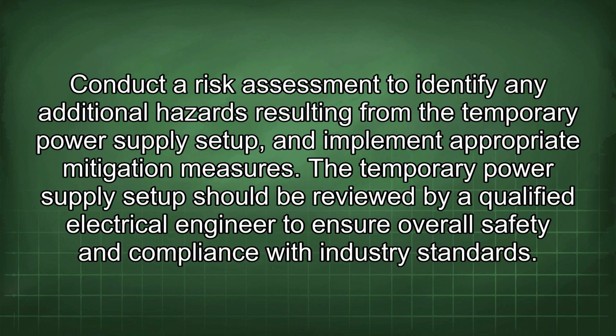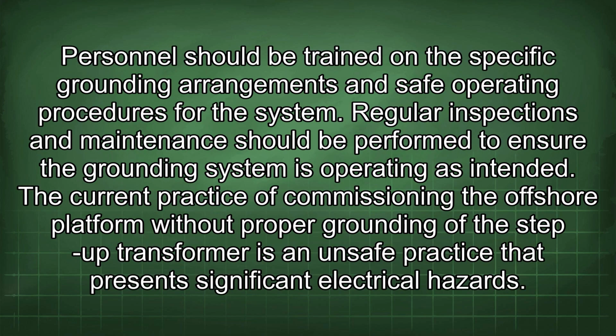Conduct a risk assessment to identify any additional hazards resulting from the temporary power supply setup, and implement appropriate mitigation measures. The temporary power supply setup should be reviewed by a qualified electrical engineer to ensure overall safety and compliance with industry standards. Personnel should be trained on the specific grounding arrangements and safe operating procedures for the system. Regular inspections and maintenance should be performed to ensure the grounding system is operating as intended.